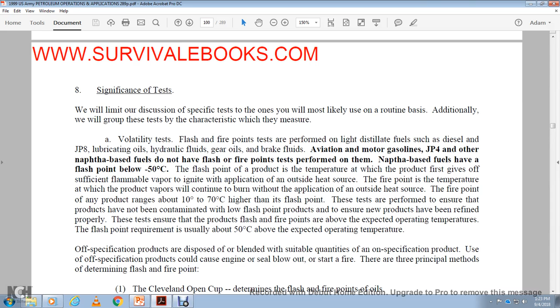The test is performed to ensure the product does not contain evidence of a low flash point, and probably ensures the new product has been refined properly. The test ensures the product flash and fire points are above the expected operating temperature. The flash point requirement is usually 50 degrees Celsius above the expected operating temperature. The off specification product is disposed of by blending with a suitable quantity of on specification product, otherwise the off specification product could damage the engine seal, cause a blow out and start a fire.